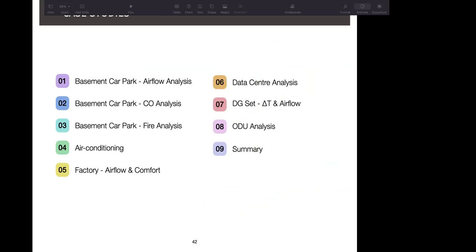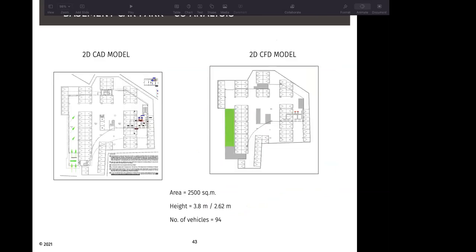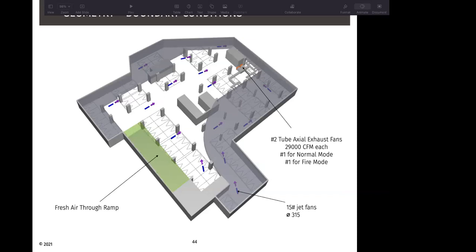Now going to the second type of basement car park analysis, which is CO analysis. Again, we are looking at a car park 2D model turned into a 2D CFD model for an area of 2,500 square meter. Now this car park has a varying height. There are some portions which are 2.62 meters, and then there are some portions which are 3.8 meters. And then the number of vehicles around the car park is 94. So for a 3D model, we can see that there are two tube axial exhaust fans, one for normal mode and one for fire mode, and the fresh air has been assumed through the ramp. 15 jet fans have been considered for the movement of air, and they have been placed. So the gray portion is the areas which have the lower height.